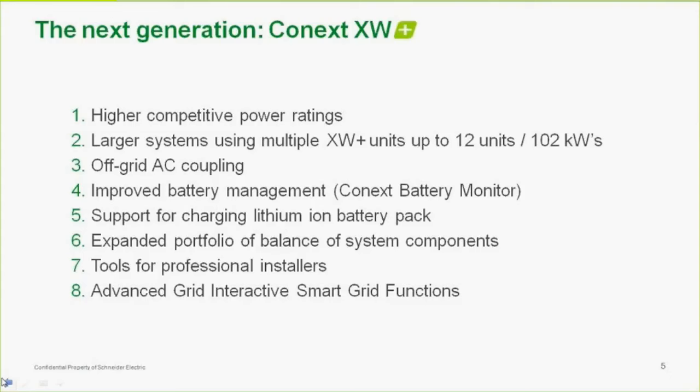And every inverter that I've ever worked with, and I've worked for all of my competitors in North America now, was designed to charge a lead-acid battery bank. And as such, connecting it to a lithium-ion, and just because you say the word lithium-ion does not mean a particular chemistry. There's lithium-iron phosphate, there's all kinds of them.